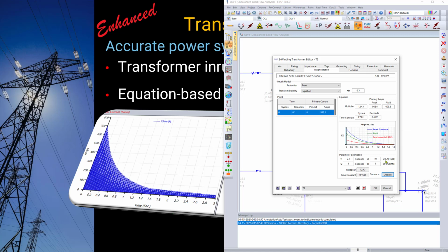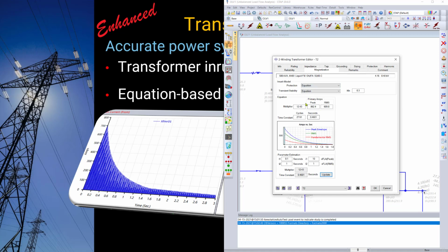This same information is then used by transient stability and can also be used by the star protection program. In order to use this with the star protection program, you can simply switch to the equation-based approach, and now transient stability and star TCCs would be using the same inrush curve that has been computed.